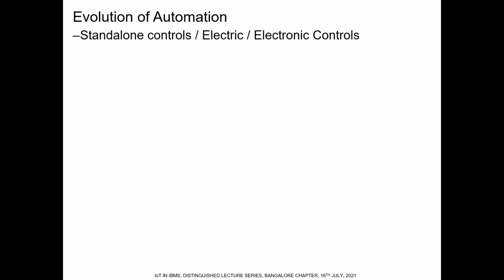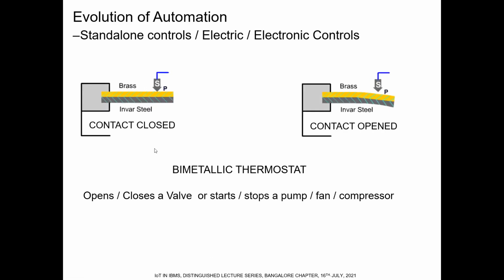Now, going back to the evolution of automation, just a couple of decades ago, we had window air conditioners that used thermostats, which used the physical principle of two metals which had different levels of coefficient of expansion. You can see here a compressor has made contact here, and a compressor has lost its contact because of the different levels of coefficient of expansion. This was the start of starting and stopping a compressor using a bimetallic thermostat. Even 20 years ago, these thermostats were in use in the industry.